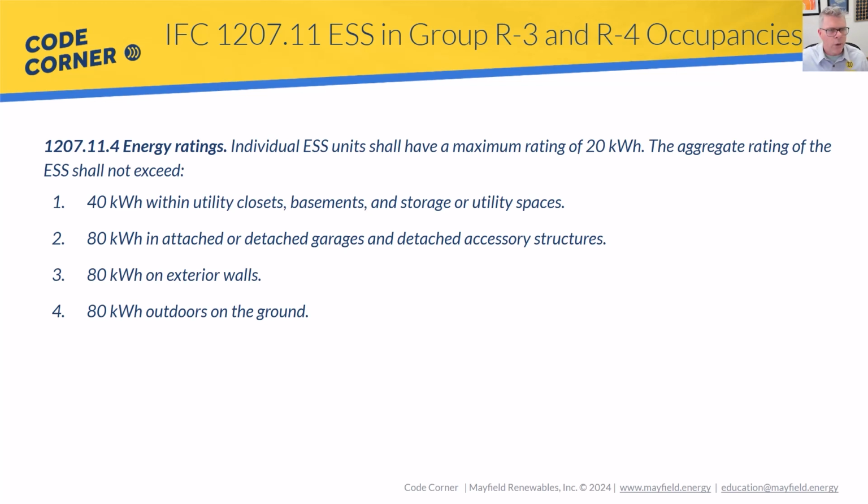One thing I'm going to point out really quick, because I know there are jurisdictions throughout the country where, while the IFC says basements is a location where you can put this, I've talked to installers and jurisdictions where basements are just off the table. So if you're trying to install ESS inside of a basement, I would highly recommend talking to your fire code officials before going down that path too far, because there are jurisdictions that are just not allowing that to happen.